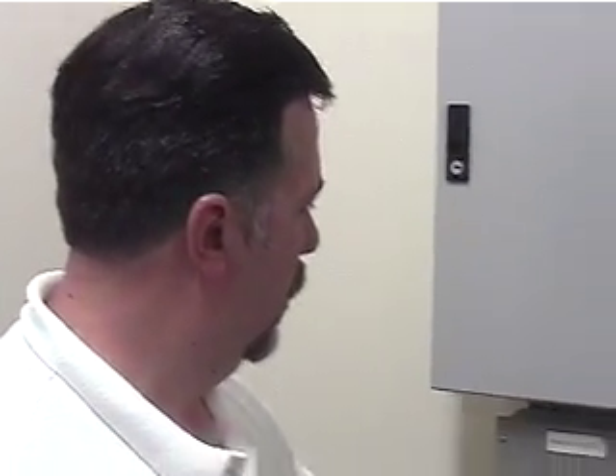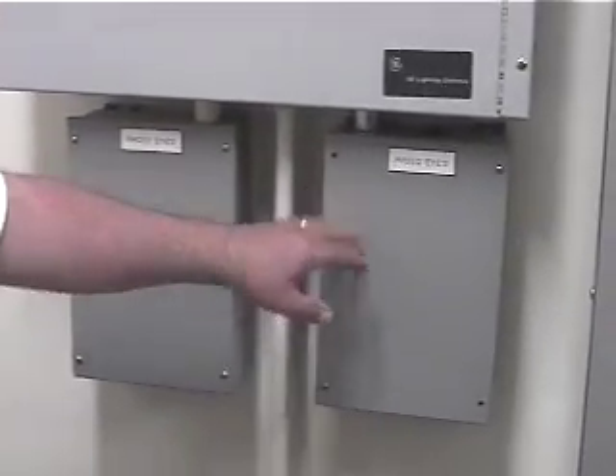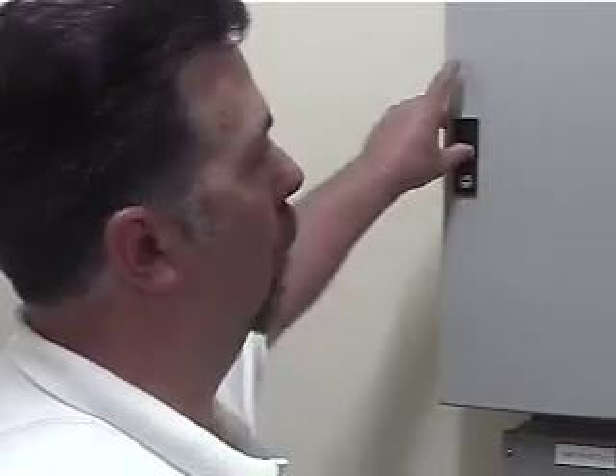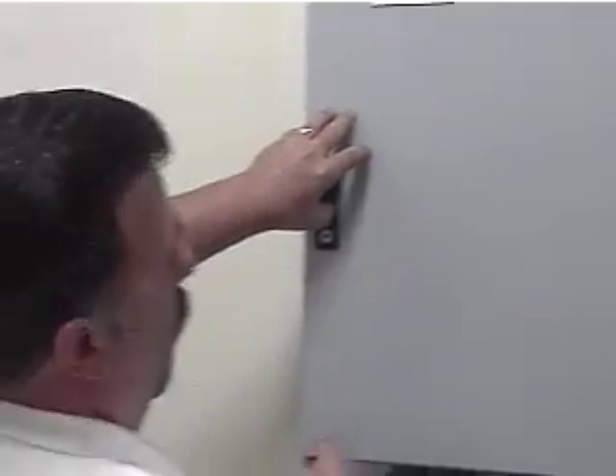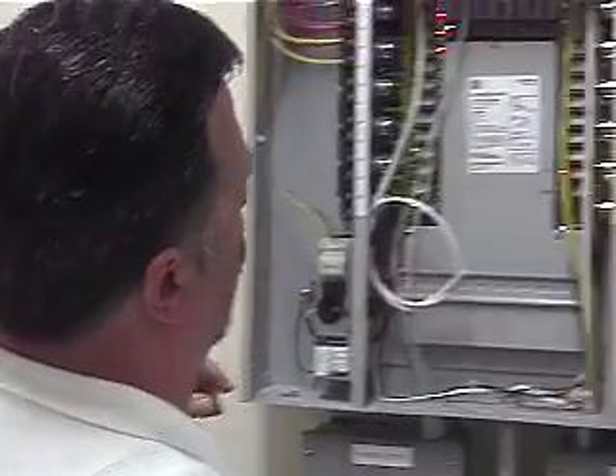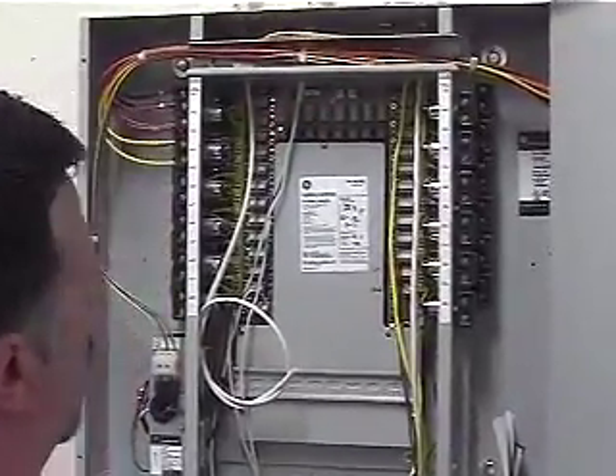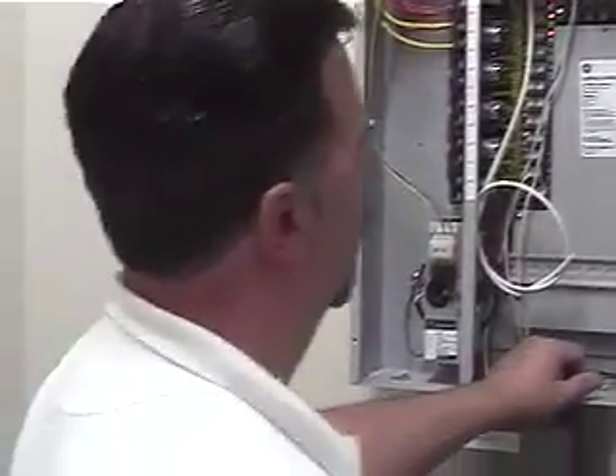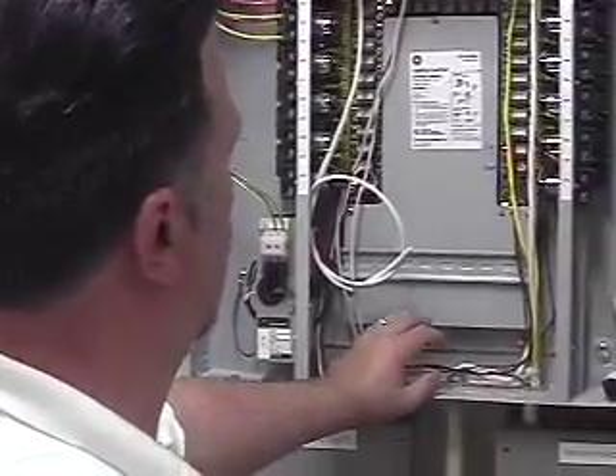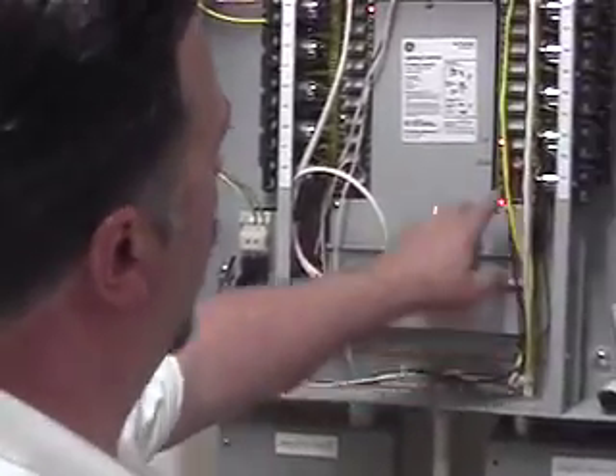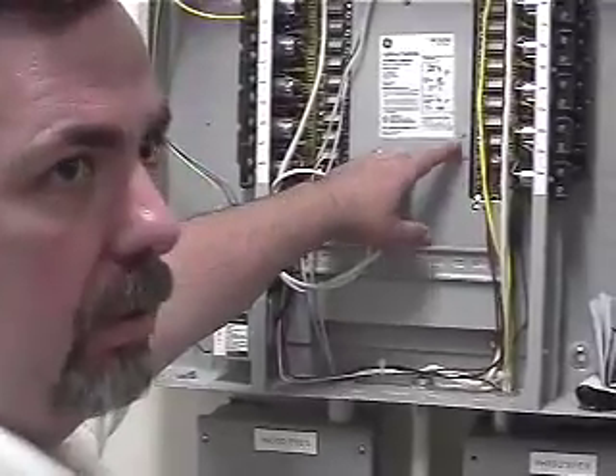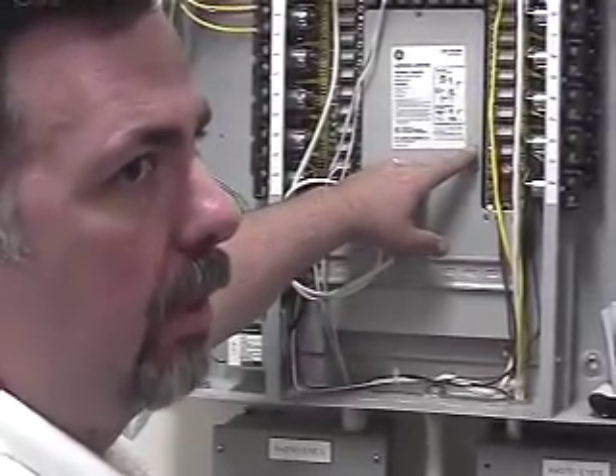So 2 of the 3 photocells that we were monitoring are in here. One of these is for, I can't remember which is which. One is for outdoor and the other one is for this west indoor. So it monitors the lighting in the atrium down here on the west end. And they're a function of the GE controls, not the... No, they're tied, well, yeah, because of the way that they function, they're designed to work with these. So we tied it into the input of the last two channels, and that's how we're getting our status.